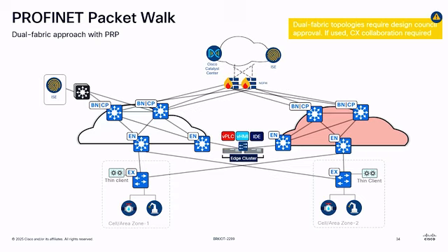It can also go the other way around. Just want to make sure that everyone understands what we are doing. Yeah, go ahead. So Sid, let me ask you some questions I always get when I present these slides to my customers. One is, you are doing safety over that. Yep. So do you need the switches in the path to be certified for safety? No, ProfiSafe in this case is a black channel protocol, so it doesn't really care what's in between. It really only cares that the endpoints are Profinet certified, and that's about it.